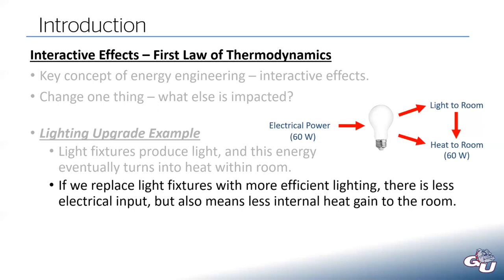And if we replace those light fixtures with more efficient lighting, say we replace all these bulbs with new LED bulbs that only draw 10 watts of power, that means there's less electrical input, which is good because we're trying to save energy. But this also means there's less internal heat gain to the room. So this might seem weird to think about, but every light that's in the room you're sitting in right now, the light above your head or the light on your desk, is essentially an electric heater. But it's an electric heater that also produces light. And really that's the purpose of it, to produce light, but it also produces heat.